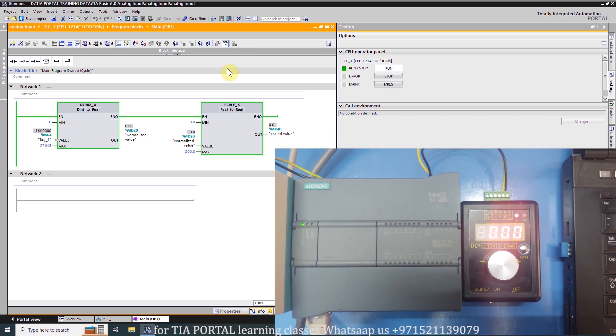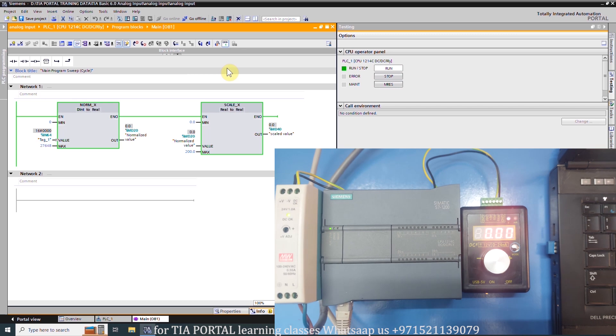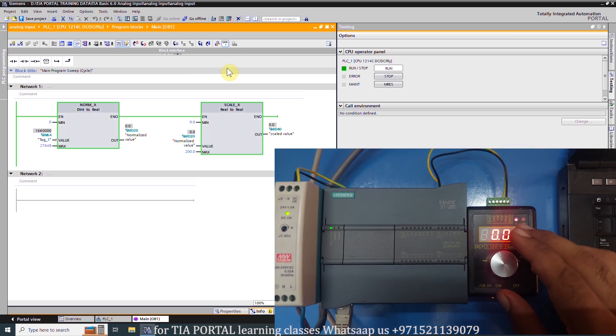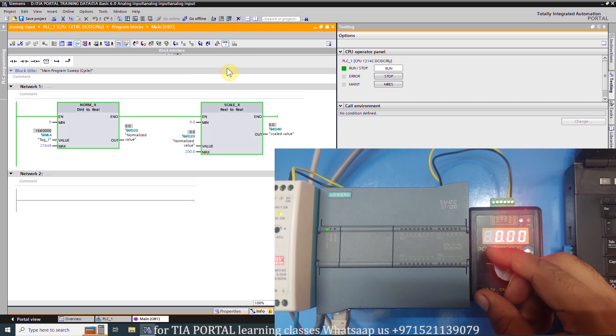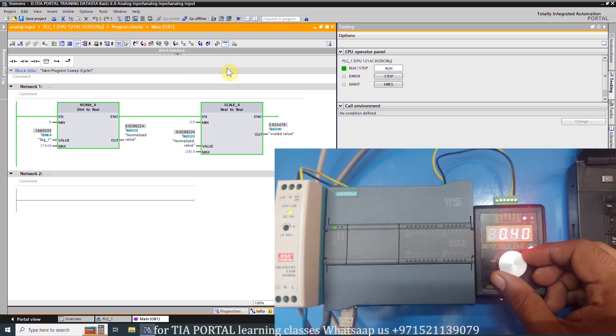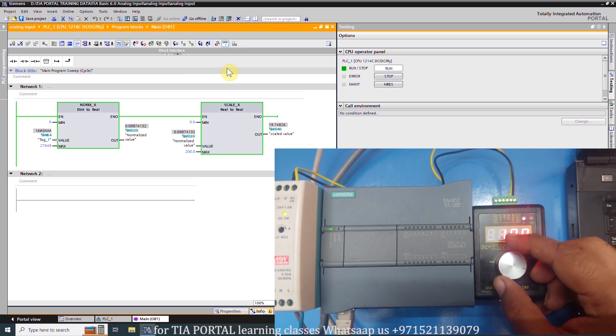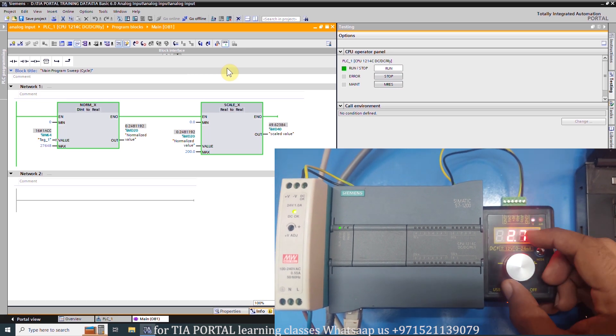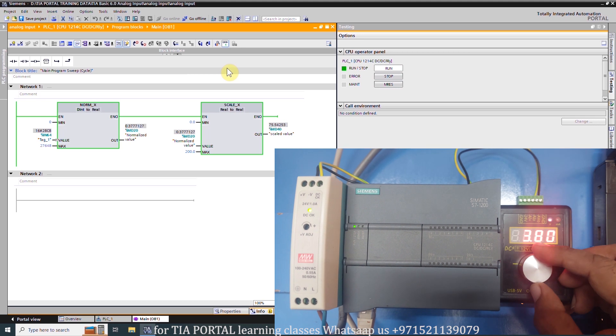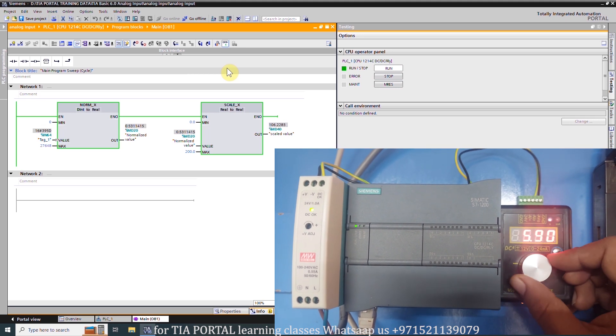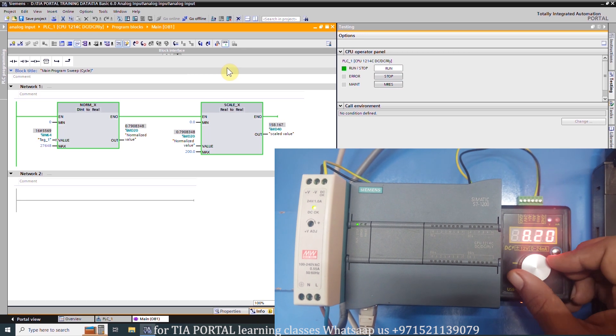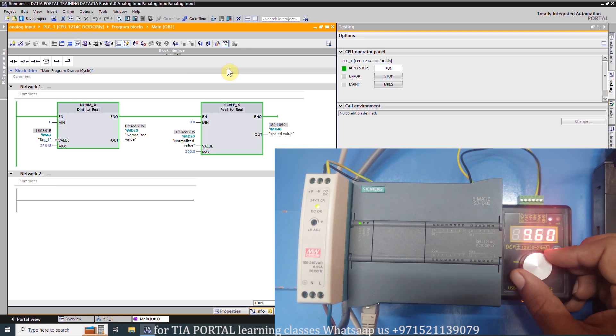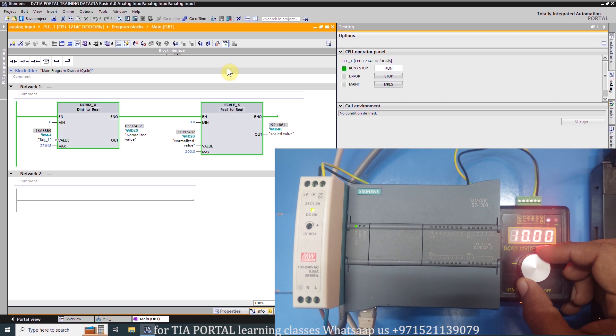As you can see, right now the input is 0 and our normalized value is 0 and our scaled value is 0, as the input voltage is 0. As you can see, now as I increase the input analog voltage, the normalized value is starting to increase and our scale function is scaling this normalized value. This scaled value is getting saved into the MD40 data register. So this is how you can use the NORM_X and SCALE_X functions to read and scale an analog input.